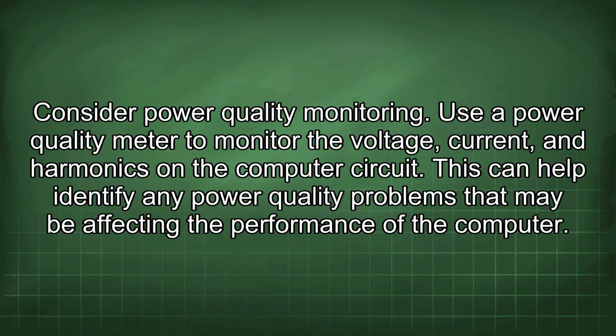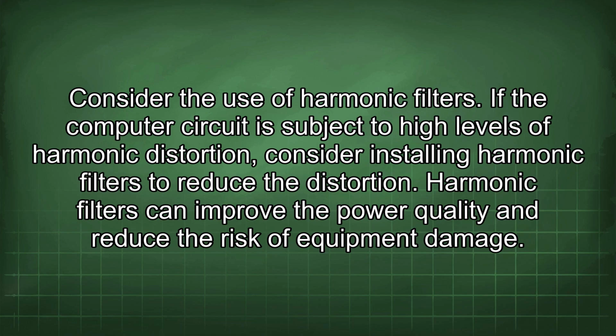Consider power quality monitoring. Use a power quality meter to monitor the voltage, current, and harmonics on the computer circuit. This can help identify any power quality problems that may be affecting the performance of the computer. Consider the use of harmonic filters. If the computer circuit is subject to high levels of harmonic distortion, consider installing harmonic filters to reduce the distortion. Harmonic filters can improve the power quality and reduce the risk of equipment damage.